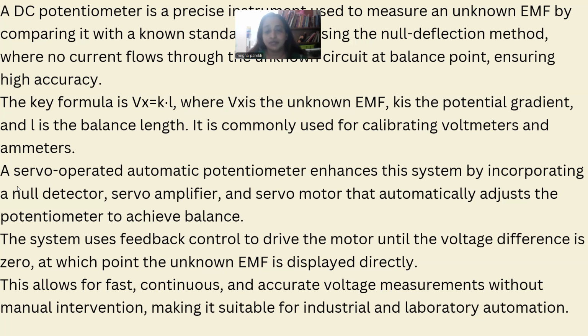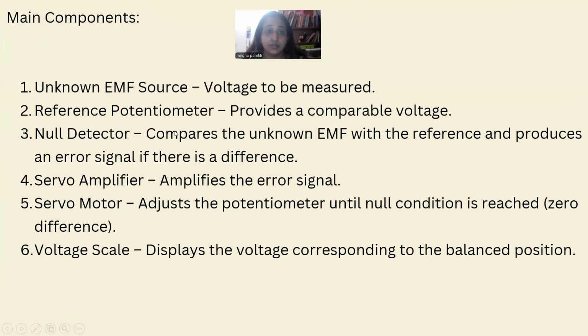The servo-operated automatic potentiometer enhances the system by incorporating a null detector, servo amplifier, and servo motor that automatically adjust the potentiometer to achieve balance. The system uses feedback control to drive the motor until the voltage difference is zero, at which point the unknown EMF is displayed directly. This allows fast, continuous, and accurate voltage measurement without manual intervention, making it suitable for measurement and laboratory automation. So let's discuss the main components.